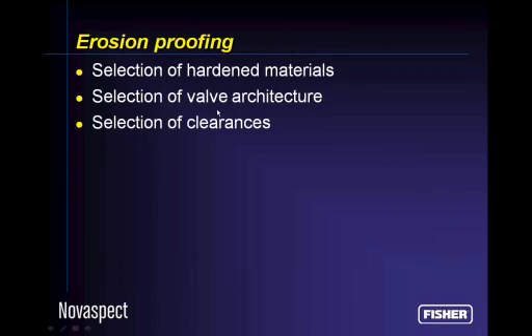For erosion, we can try to erosion-proof your control valves by the appropriate selection of very hard materials for the trim components. Maybe even the body itself needs to be made of a very hard material. Maybe we have to have a hard liner inside to resist the effects of these particulates that are coming through and wanting to erode the valve away. Sometimes we'll use a particular valve architecture. We might use an angle valve instead of a straight-through valve in order to make the fluid not make so many turns within the valve, so that we don't give these erosive solids an opportunity to spend much time in the vicinity of metallic parts. Basically, get the flow straight through the valve.